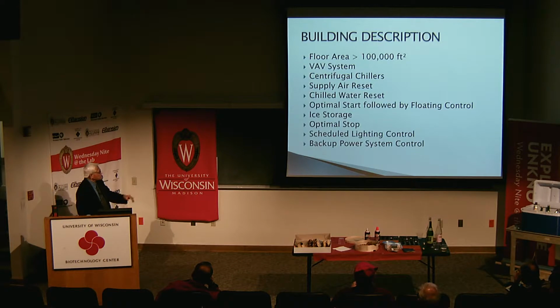The next one is scheduled lighting control, which you can possibly do: take off a bank of lights in the common areas, not the occupied zones, but the common areas such as hallways, and shut them off when there is not much activity, maybe from 9 in the morning to 11 o'clock in the morning, when all the occupants are in their offices working. The same thing is true in the afternoon, maybe from 2 o'clock till 4 o'clock. Or you can use motion detectors to do that.